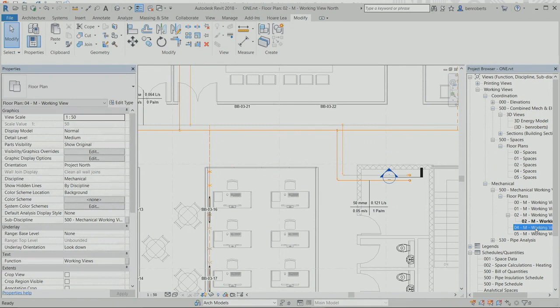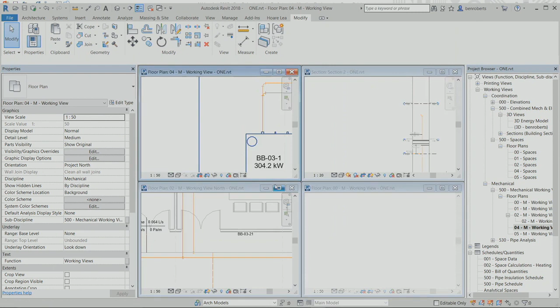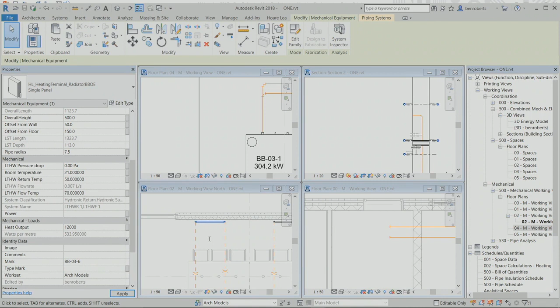And that's adding up all the way back. If I go back to my boiler, the heating duty is changing. So again, just to labour the point, if I change a load in my radiator here, for some reason it becomes... oh look, they're 600, I told you they were 1,000, I lied. If that becomes 12 kilowatts, it's going to update all the way back at the boiler.